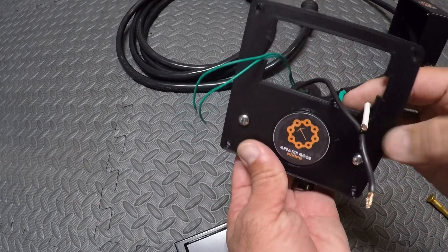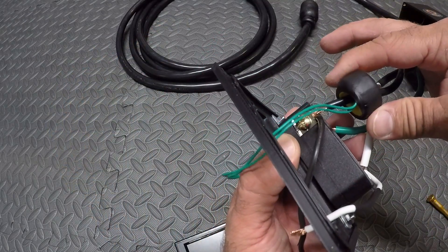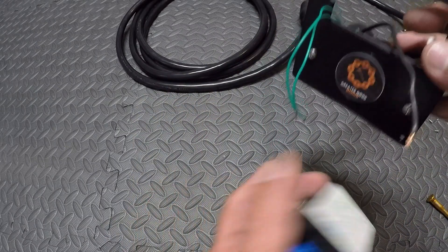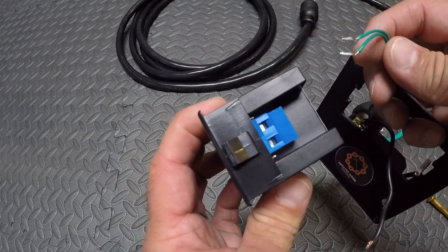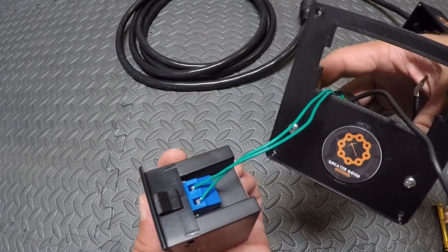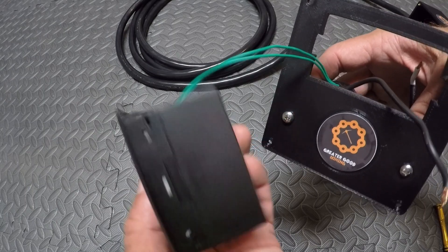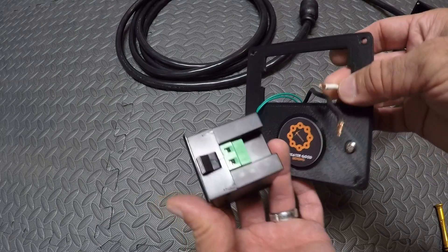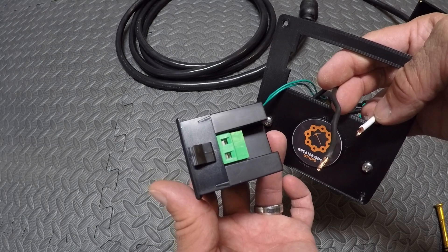Bring your wires through the front of the faceplate here. The donut — where the green wires are coming off of it — is what we're gonna wire up first. Just make sure the ends are stripped and we're gonna connect the green wires to the blue side of the DROK power meter. Our green wires are attached from the donut to the blue side. Next we're going to attach our two hots — the white and the black jumper that we made — to the green side of the DROK power meter.